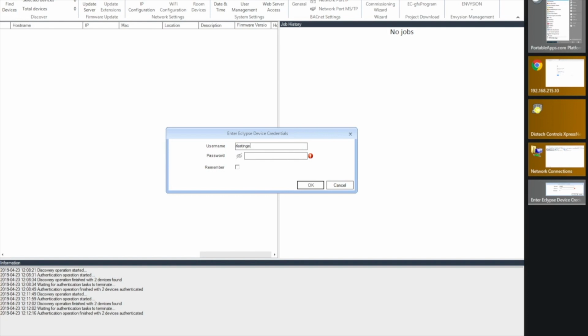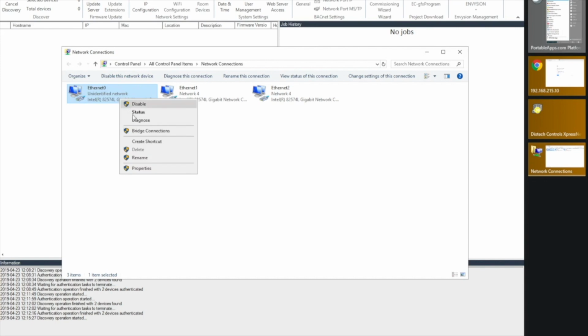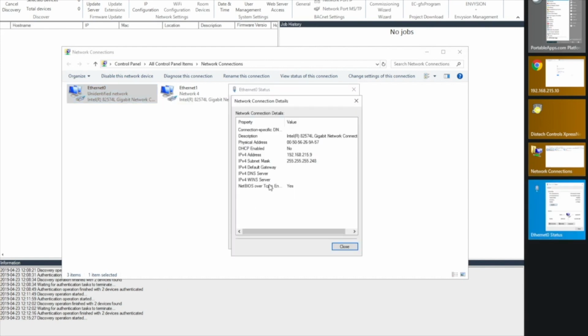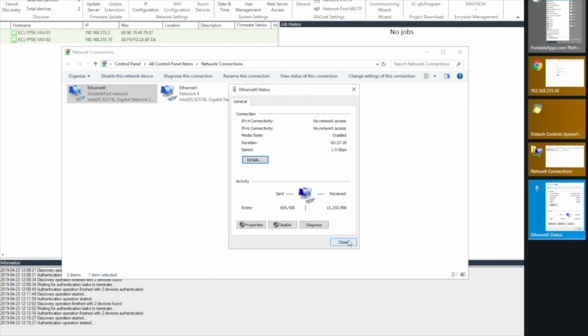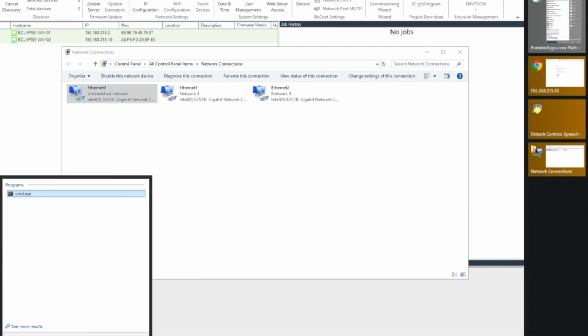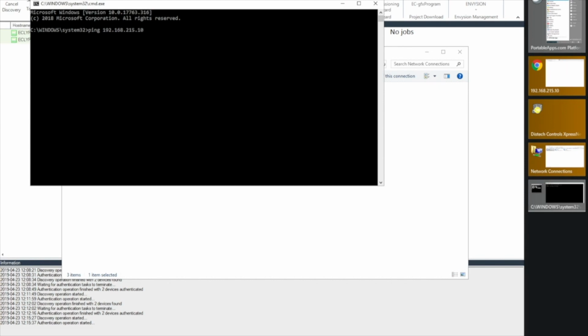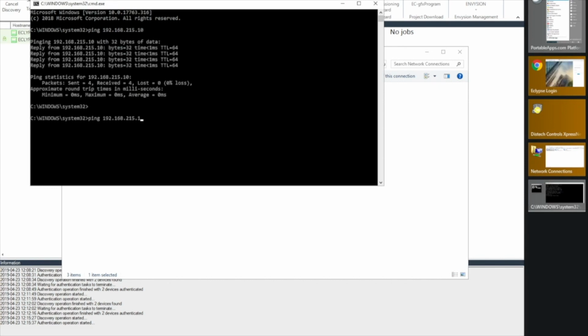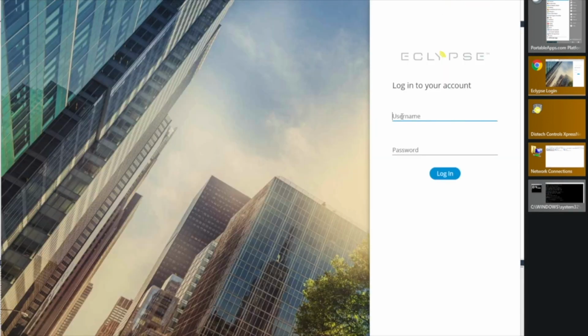And here I'm going to find the devices to make sure that I should only see the one on the subnet I'm on now. I can still discover the other one, but it won't show up as a valid connection. So I'm on the second subnet. And there I can see both, since that's broadcast traffic, and we can broadcast across subnets, which you see there. I see both controllers, but I won't be able to ping the controller on the second subnet, which you'll see me try to do here. So let's log into the controller, and we'll attempt to ping the controllers from one another to show that we can't talk.